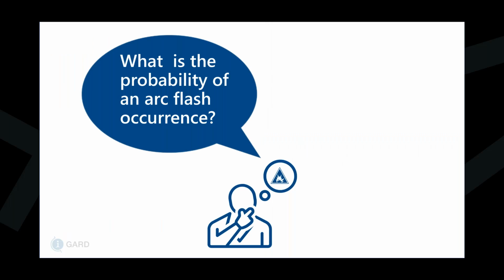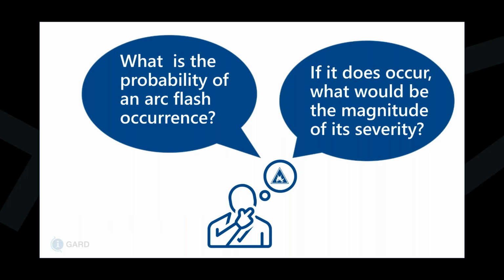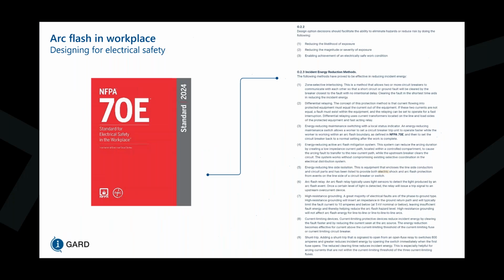So the questions that come to mind are, what is the probability of an arc flash occurrence? And if it does occur, what would be the magnitude of its severity? In NFPA 70E, in Annex O.2.2, it says that design option decisions should facilitate the ability to eliminate hazards or reduce risk by doing the following: reducing the likelihood of exposure, reducing the magnitude or severity of exposure, and enabling achievement of an electrically safe work condition.